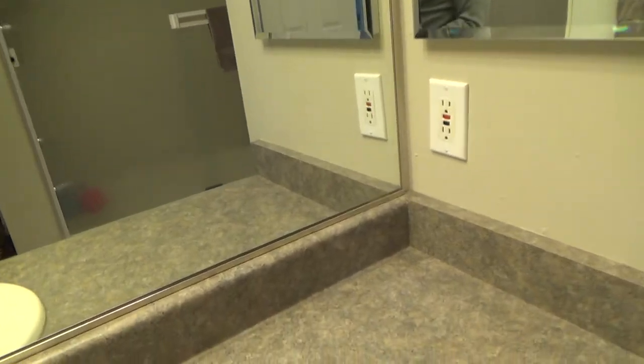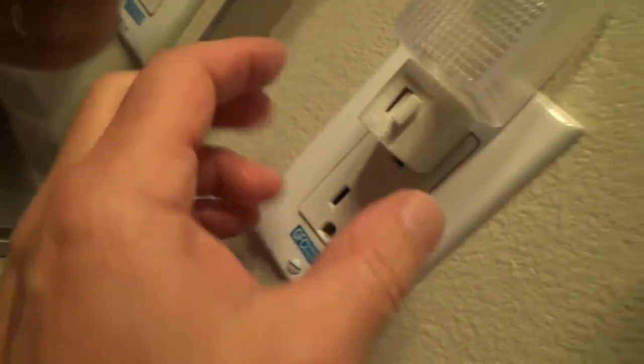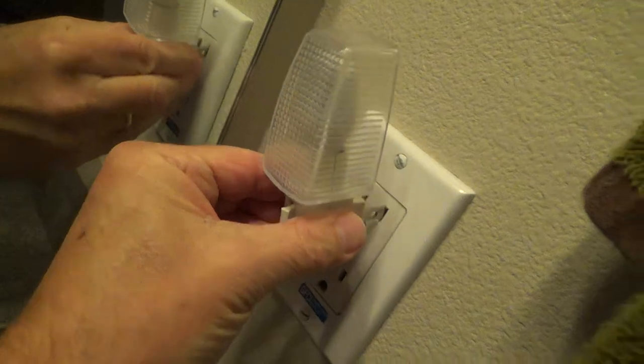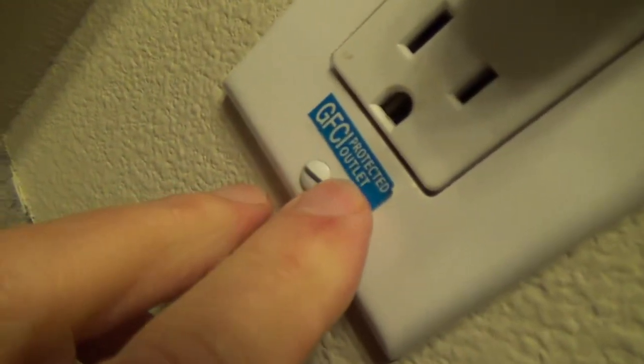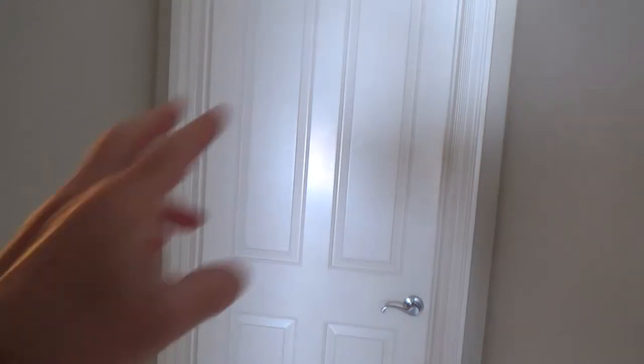Why would they do such a thing? We look at this one here — there's a GFI in one bathroom, but over in this other bathroom, you see there's no GFI electrical outlet there, but it says 'GFCI protected outlet.' That means this electrical outlet is tied in to the other one in the other bathroom. And remember, there were two breakers in the panel that said bathroom GFI — that didn't mean two different circuits for these two particular bathrooms. The other bathroom upstairs is connected to a separate GFI or separate electrical breaker.